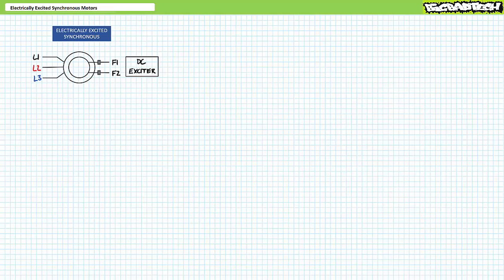However, be aware other types of exciters exist, including those mounted on the rotor. We'll examine three-phase AC rectifiers central to the operation of exciters in greater detail in later lectures. Because an electrically excited synchronous motor necessitates both a three-phase AC source for the stator and another DC source for the rotor, you may hear them referred to as doubly excited synchronous motors. Getting DC electricity from a stationary external exciter to a rotating rotor presents a structural challenge not encountered with squirrel cage induction motors, which operate using the principle of induction and do not necessitate an electrical connection to the rotor. Despite the advantages we've yet to discuss, this is perhaps the electrically excited synchronous motor's greatest weakness.